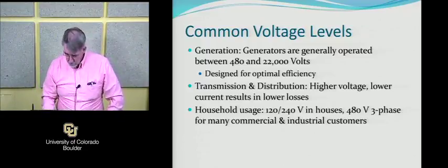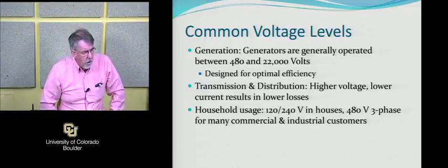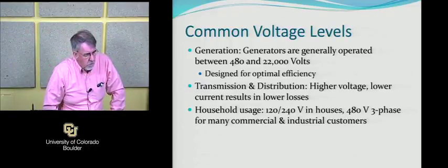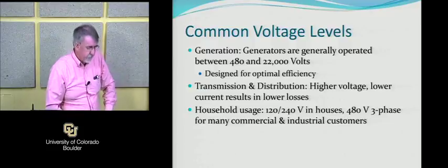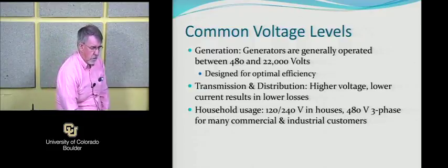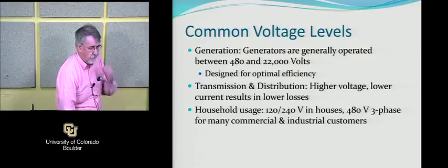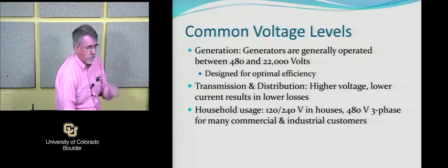Just a quick question while we're on the topic of voltages. Why, if I call the utility and say I want electrical service at this location, they say you can have 120, 240, 3-phase, but then you still have to put in a transformer? Does that mean the actual distribution wires aren't at those voltage levels? It seems like if you're putting in a transformer, you could put in whatever voltage, you could change it. The phases are a separate thing, but...